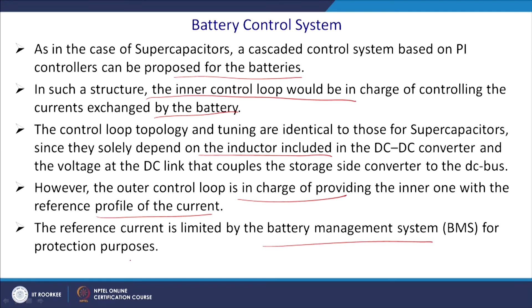Since they solely depend on the inductor included in the DC to DC converter and the voltage at the DC link that couples the storage side of the converter to the DC bus. However, the outer control loop is in charge of providing the inner one with a reference profile of the current. The reference current is limited by the battery management system for protection purposes, and generally if it is a lead acid battery, your maximum charging current cannot cross 10% of your AH value. So, that kind of limitation will be put by the battery management system.